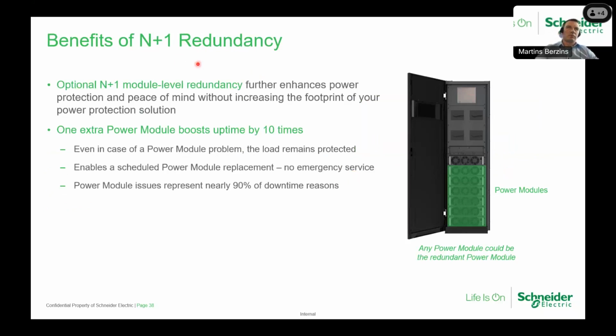So what is the benefit of having N+1 redundancy, or one extra redundant power module? 90% of the failures or downtime are typically caused by the power modules. So having one extra power module always available increases the uptime around 10 times. So in this case, if, for example, one power module would fail, the rest of the power modules would continue working, and then there will be no downtime on the UPS.